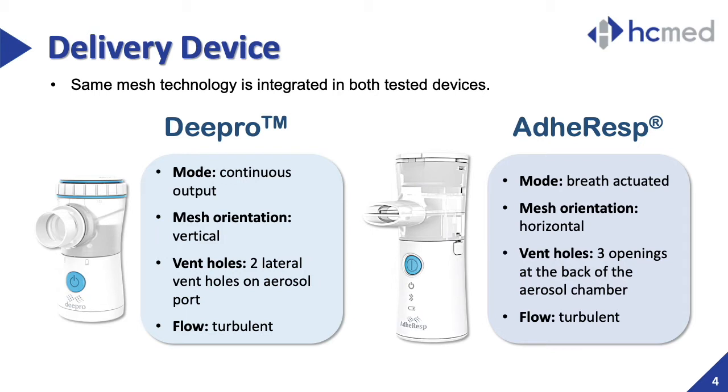The two mesh nebulizers used in the study are embedded with the same mesh technology. The Deepro mesh nebulizer operates under continuous mode with a mesh membrane in vertical position. This device comes with two lateral vent holes on its aerosol port that face one another, introducing turbulence into the airflow. On the other hand, the ADHERESP mesh nebulizer is a smart breath-actuated device that has a horizontally-oriented mesh membrane with three openings as vent holes that allow for turbulent airflow to deliver the medication.